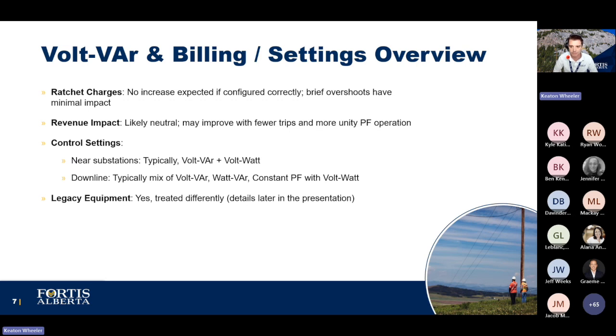Settings. So what settings will be used here? Now, obviously, there's default settings in IEEE 1547. There's other default settings in other standards as well. The control mode set points are going to be provided by FortisAlberta for the DER, and the DER will be responsible for implementing these settings. Now, these set points are determined by studies that are conducted by our in-house engineering team. But generally speaking, what you'll see is for sites near the substation, Volt-Var with Volt-Watt will typically be used. And for sites further down the line, you're going to see any combination of Volt-Var with Volt-Watt, Watt-Var with Volt-Watt, and constant power factor with Volt-Watt. Now, again, this is based on studies and it's based on the system conditions. So each one of these is based on a specific site location.